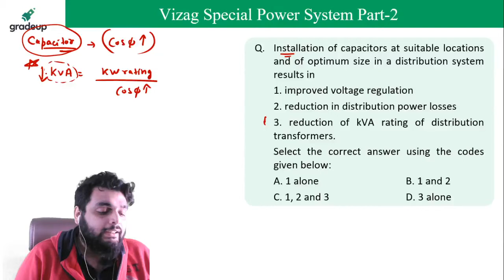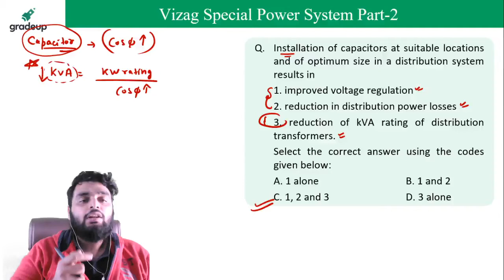So if I apply the capacitor, cos phi increases. If cos phi increases, the kVA rating will decrease. It means the third statement is correct. About the first statement, obviously it will improve the voltage regulation because the power factor will also improve. Reduction in distribution power loss is also correct. So all the statements are correct: options 1, 2, 3. Options 1 and 2 were easy, you know the application of capacitor. Option 3 was a tricky one. You can see kVA rating is equal to kilowatt rating divided by cos phi, so if cos phi increases, kVA rating will decrease.